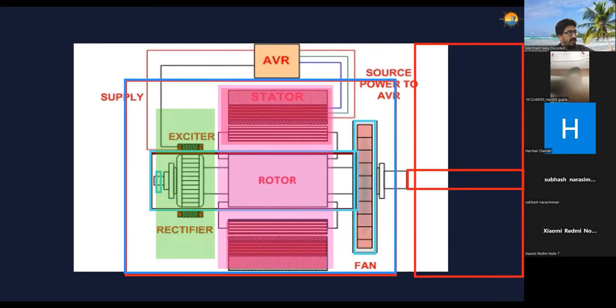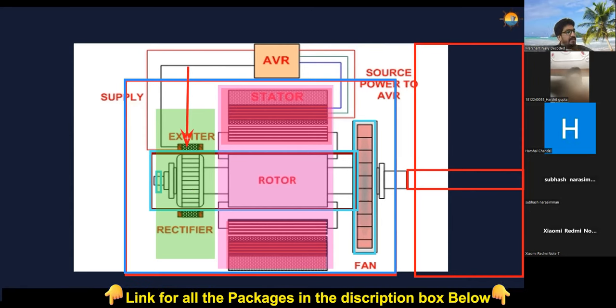Now, the working principle remains the same in both of them, which is Faraday's law of electromagnetic induction. So what we do is we provide a DC current to the exciter stator. So exciter, there's a stationary part, we call that stator or the outer shell you can say. And we provide a DC current. So because of that DC current in the stator part, it becomes an electromagnet. And inside of this, this area, we have a three phase coil.